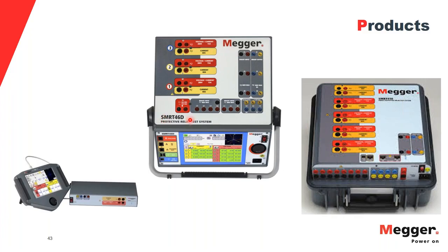46D unit that has the onboard display, and the software on the onboard display is exactly the same software that you get on the PC. So you can program the directional element trips on the onboard display itself. This unit has a maximum of 6 current channels and 4 voltage channels. So I have my 3 voltages and 3 currents that I need to test my directional elements. I can get it from this box or even this unit.